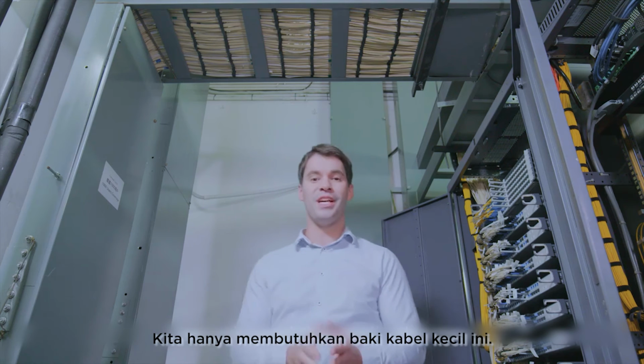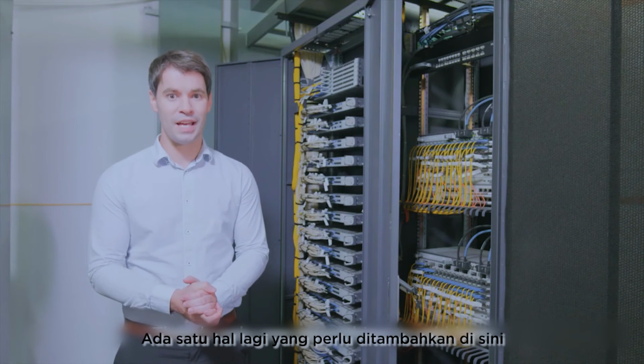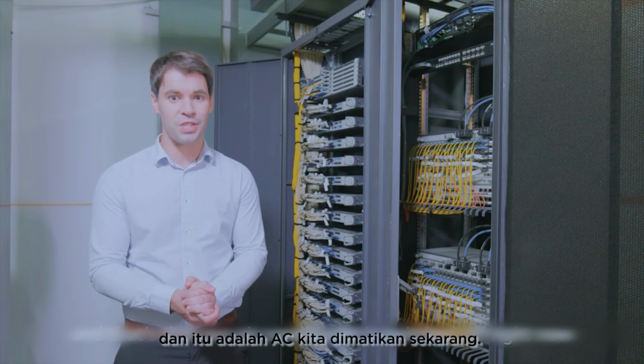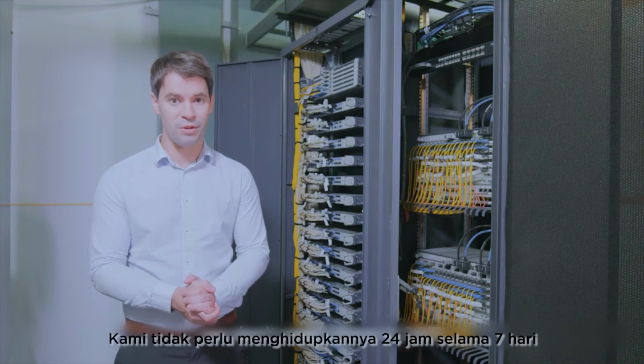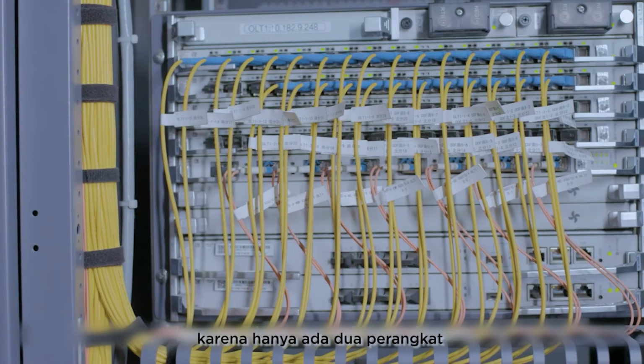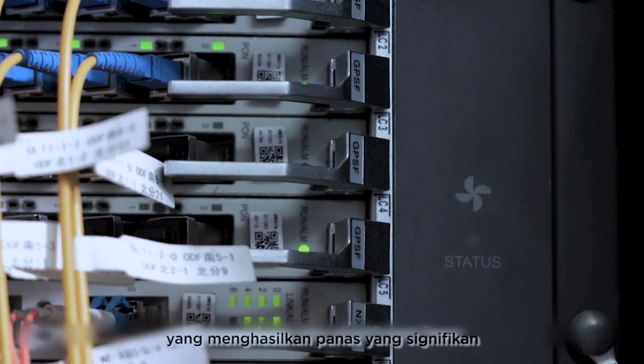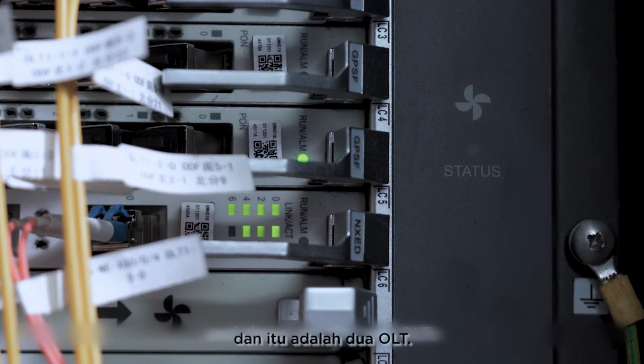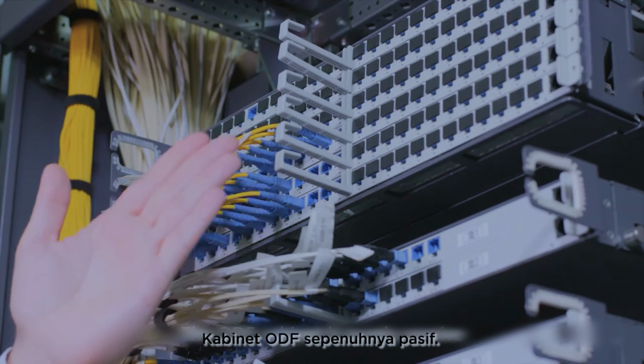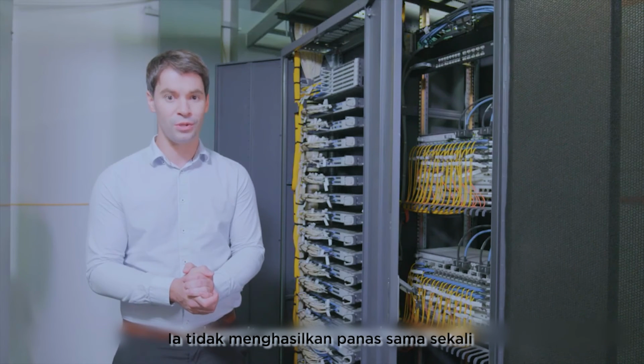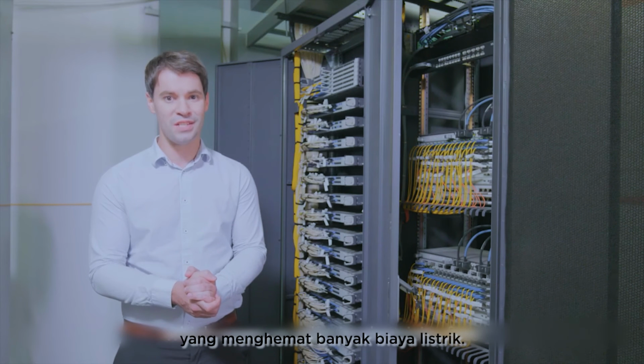There's only one more thing to add here, and that's that our air conditioner is switched off right now. We don't need to run it 24/7 because there are only 2 devices that produce any significant heat, and those are the 2 OLTs. The ODF cabinet is purely passive. It doesn't generate any heat at all, and it cools down naturally, which saves us a lot in electricity fees.